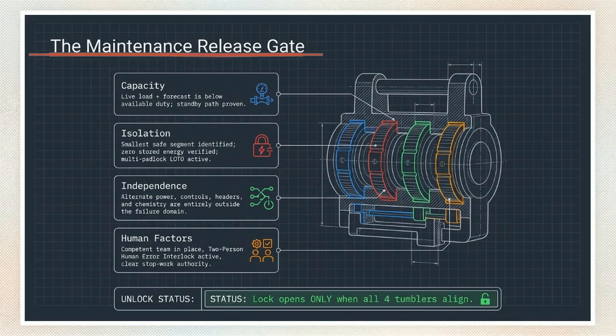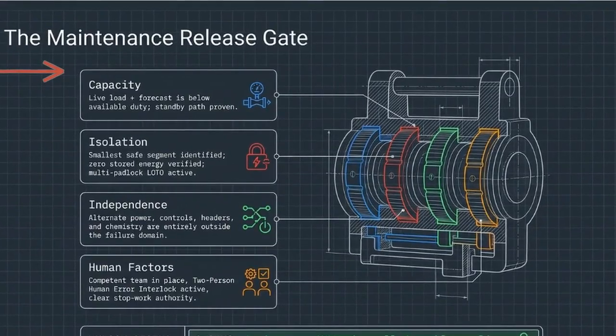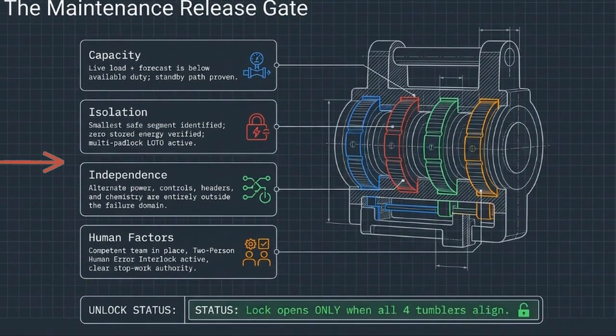No physical work starts until 4 independent operational conditions are simultaneously verified and satisfied. The live load capacity must be proven below available duty. Isolation requires identifying the smallest safe segment with 0 stored energy. Independence ensures alternate control paths are entirely outside the failure domain. Finally, human factors activate a 2-person interlock with clear stop work authority.